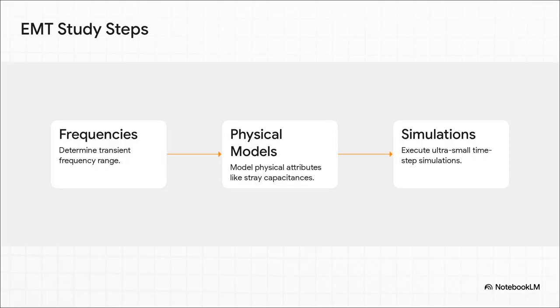Executing an EMT study isn't just plugging in numbers. It is a rigorous, highly specialized procedure. First, you must determine the exact frequency range of the transient you're investigating, whether it's an SFO or a VFFO. Second, you have to build high-fidelity models of the physical components. This means intentionally modeling stray capacitances, mutual inductances, and structural core characteristics that you would normally just ignore in a basic load flow study. Finally, you execute the simulation using those microsecond to nanosecond time steps to capture the true rate of rise and amplitude of the shockwave.